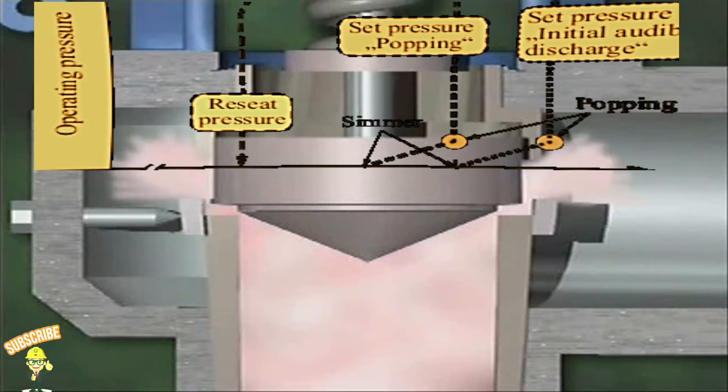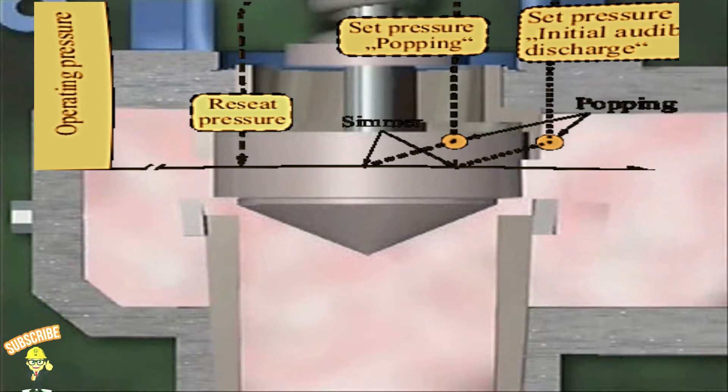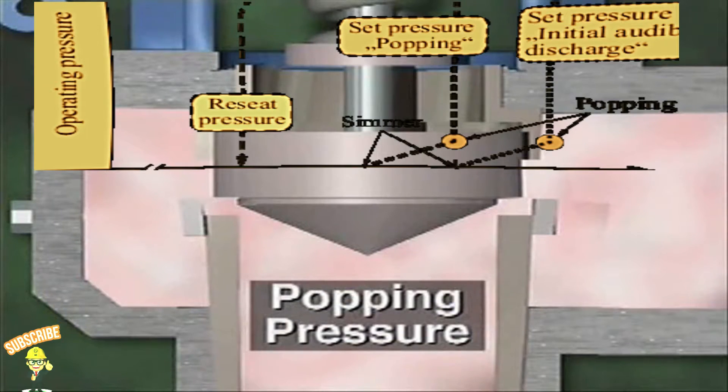As the disc lifts, the lip of the disc is suddenly exposed to system pressure. Since a larger area of the disc is now exposed to the pressure in the system, more force is being exerted on the bottom of the disc. This increased force overcomes the spring tension and causes the disc to pop open to about a 60% open position. When the valve's popping pressure is reached, the valve should open with a clean and sudden pop.